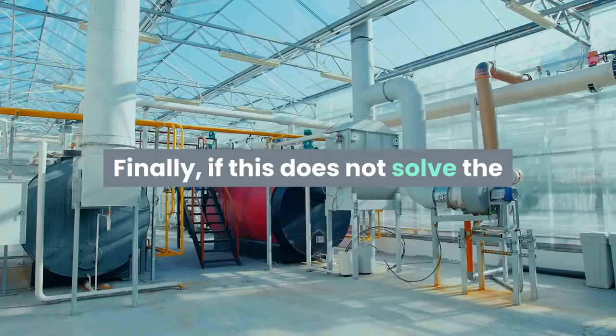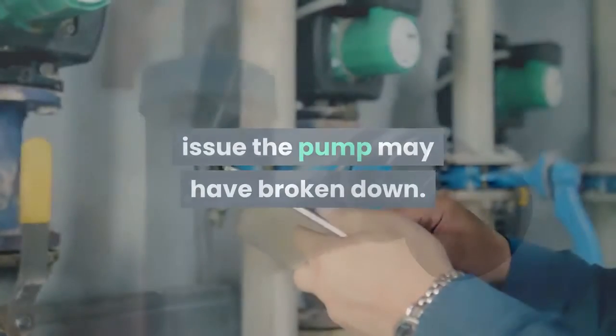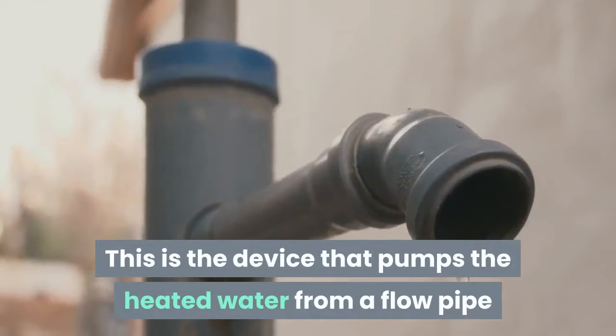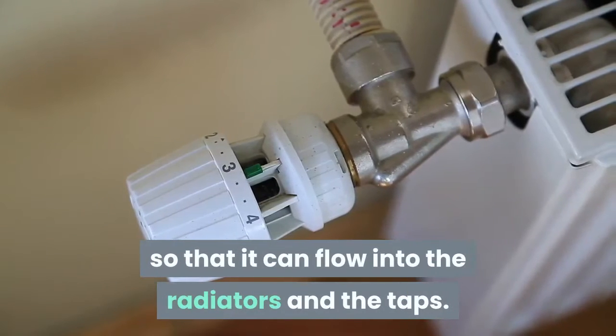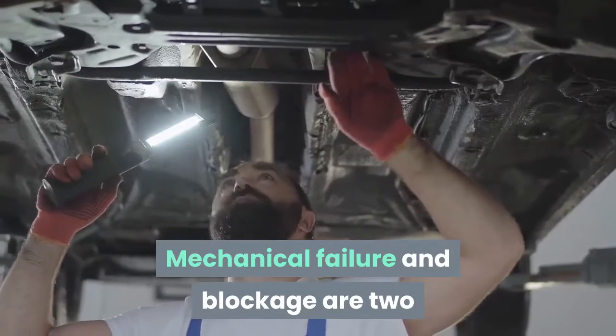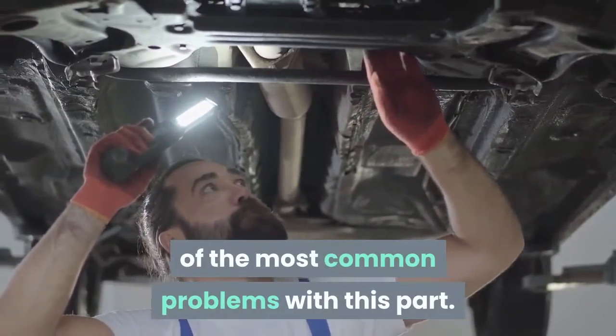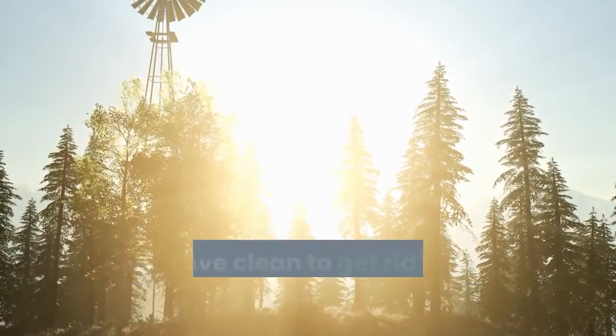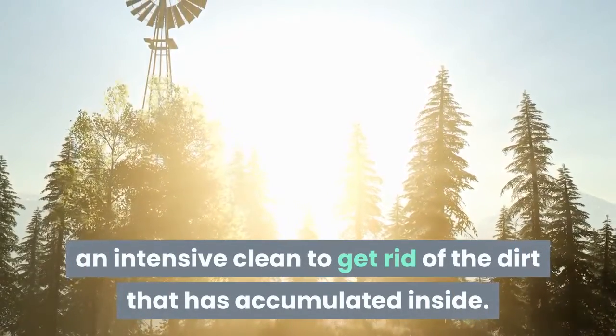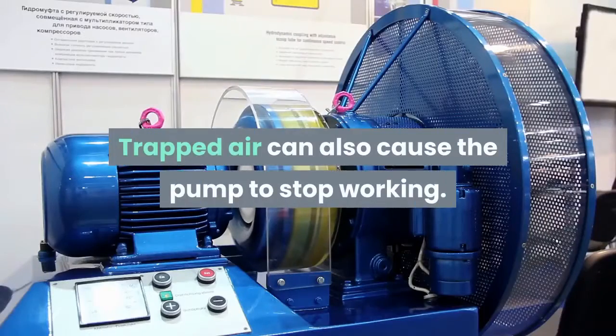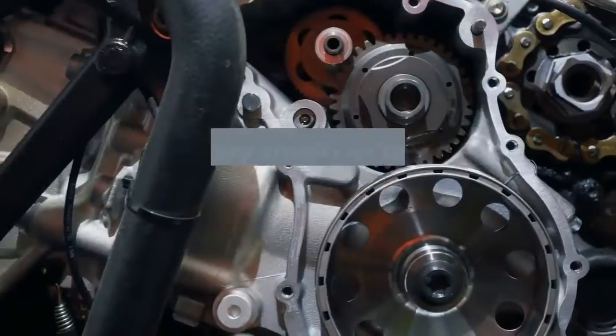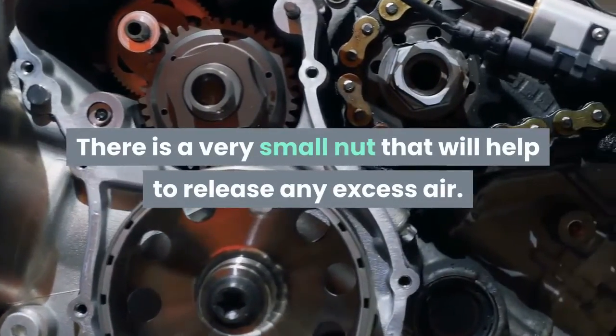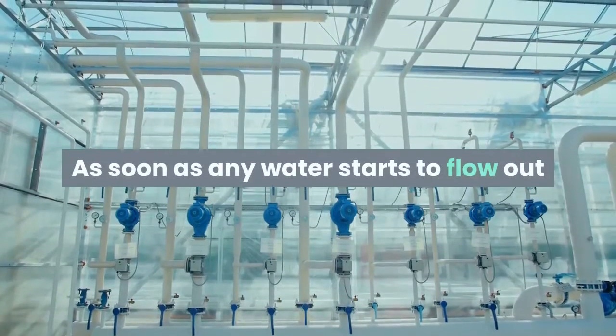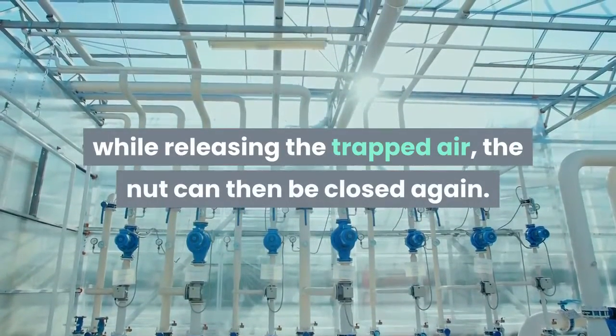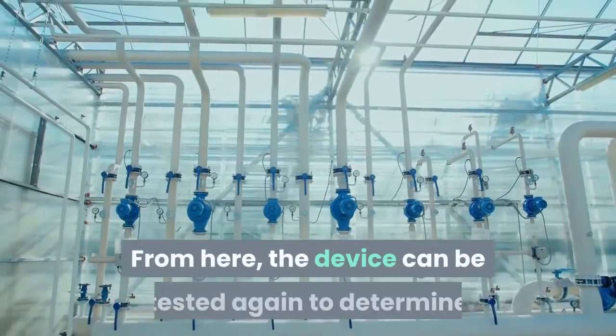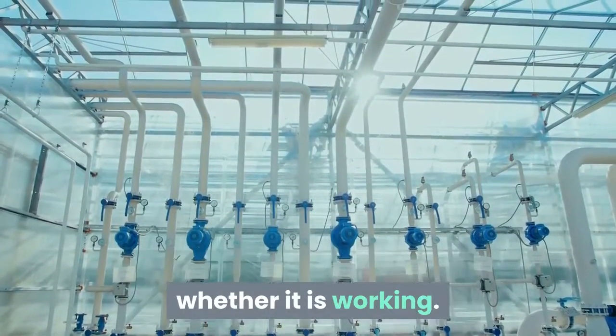Finally, if this does not solve the issue, the pump may have broken down. This is the device that pumps the heated water from a flow pipe so that it can flow into the radiators and the taps. Mechanical failure and blockage are two of the most common problems with this part. If the pump is clogged, it will require an intensive clean to get rid of the dirt that has accumulated inside. Trapped air can also cause the pump to stop working. There is a very small nut that will help to release any excess air. As soon as any water starts to flow out while releasing the trapped air, the nut can then be closed again. From here, the device can be tested again to determine whether it is working.